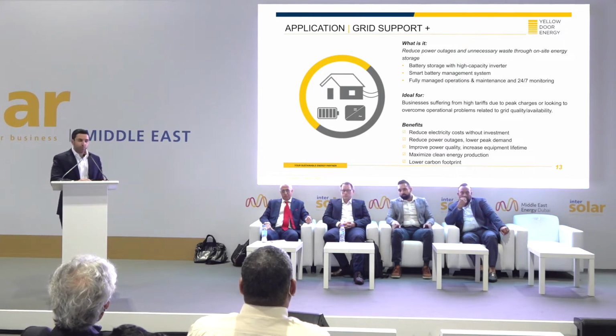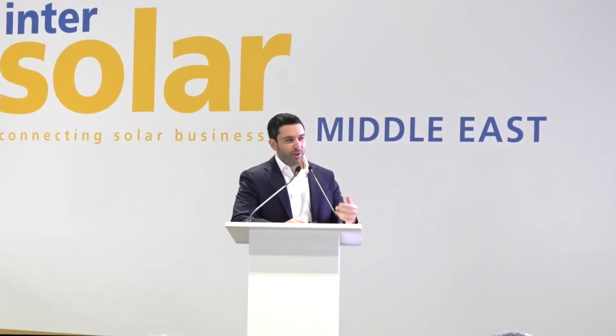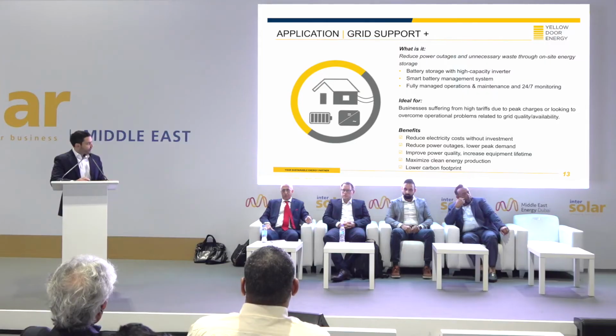In a lot of the markets, we also see that the utilities charge a very high peak tariff. So whenever you have a very high consumption for part of the day or for a few hours, they charge you a lot for your capacity that you are asking from the grid. So what this system can do is actually do peak shaving. Whenever the grid charges you for a very high peak charge, the battery will take over when there's a peak and then charge from the grid when the peak doesn't exist anymore or when you reduce your load. So that's a third application.